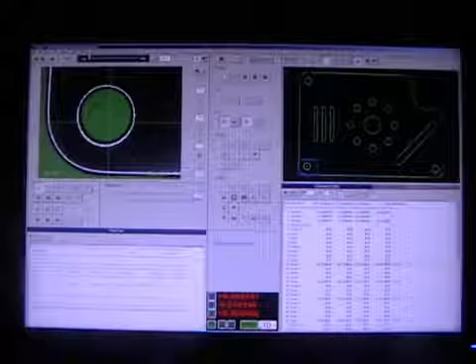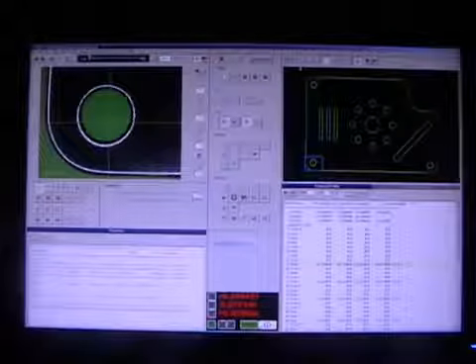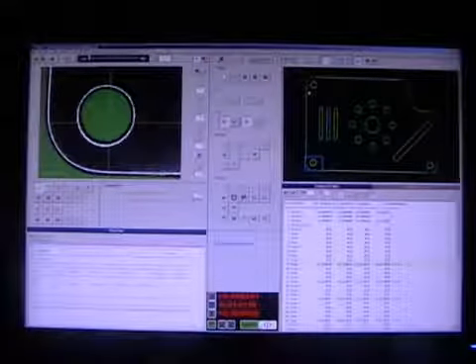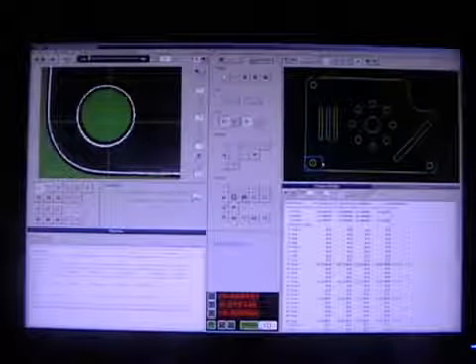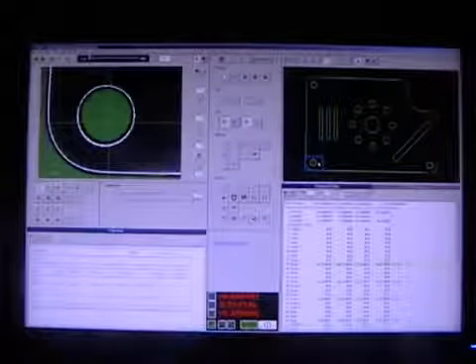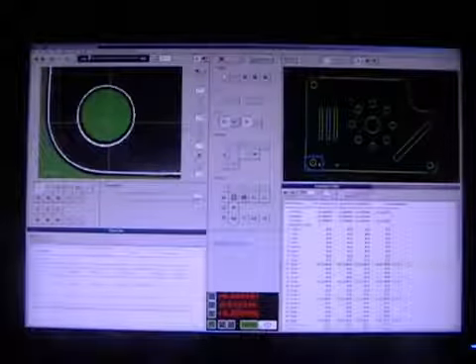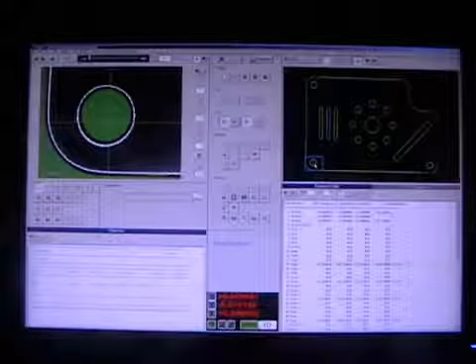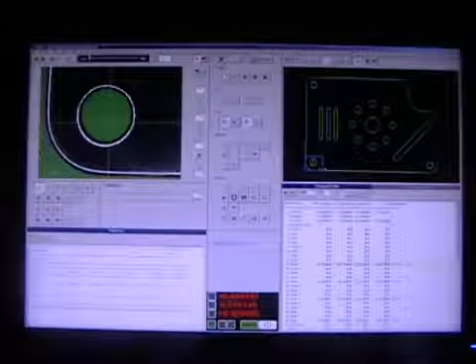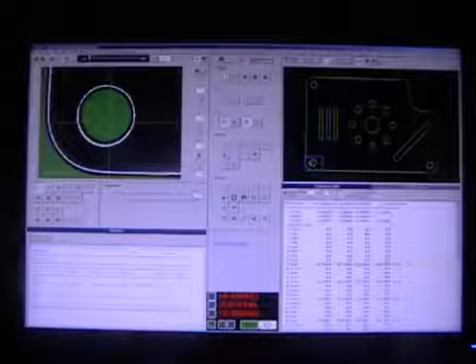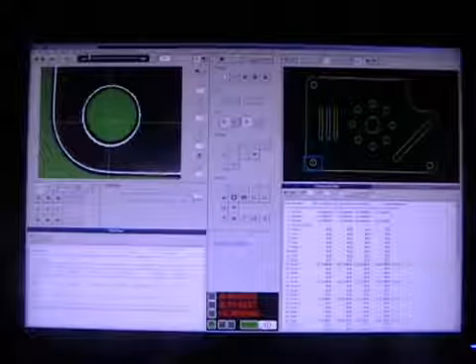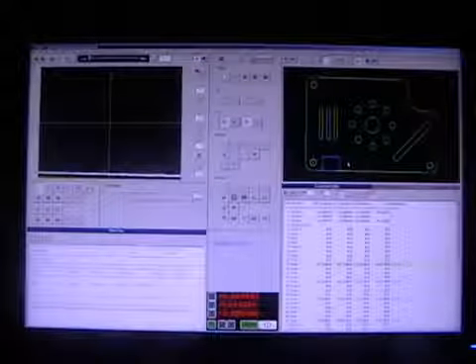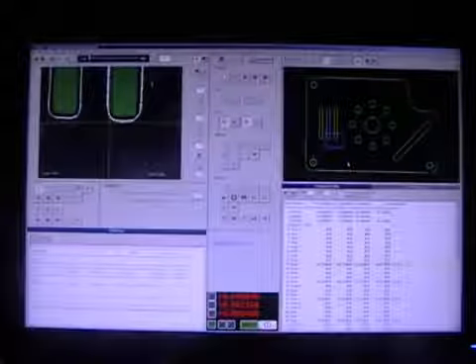And there are the magnifying glasses, the plus and minus to zoom in and out. You also have buttons here to save the image at this section of it or to print it. In the model itself there are several standard representations here. Here the arrows that we see in the lower left corner in the center of this circle represent our current zero reference. So the red arrow pointing in the direction of the positive x axis, the green pointing in the direction of the positive y axis. There's actually a yellow arrow there pointing directly out to the screen, that's the positive z axis. The blue box we see represents the area that we can view in the live video image. So as we move the stage, the blue box moves, the live image of the video updates here and the blue box location updates over on the model window. So using that we can navigate where we are on the part itself.